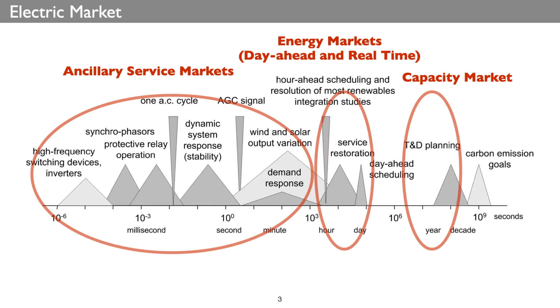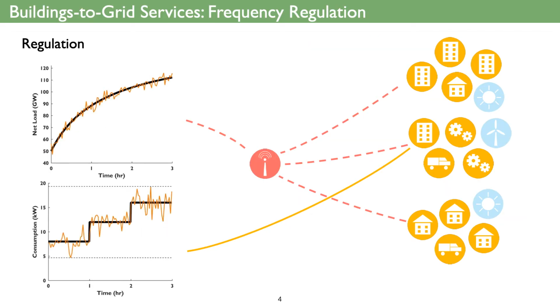Frequency regulation, as one type of ancillary service, requires a power balancing at an interval of seconds. Providing frequency regulation by buildings actually means the building should be able to continuously adjust its power outputs to track a reference signal received from power grid.